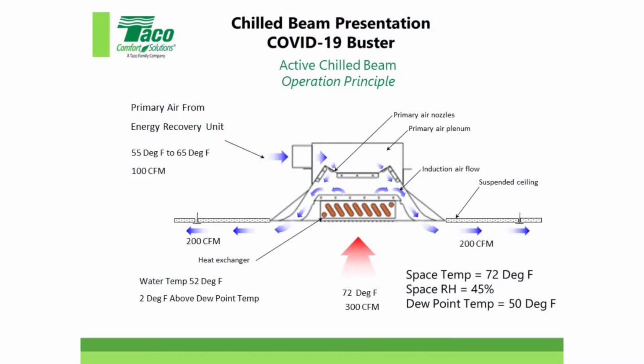I had to borrow this, so here's kind of the engineering associated with this. You can see right here the primary air coming from the energy recovery unit. There are different temperatures that you might be going in there. It's very gentle, very small. You're going to see an air flow pattern very shortly. And there's the induction. The air comes in right here, see how it comes in? It goes through some nozzles right here, induces the air to come up here, and then this gentle air comes down and just falls down into the zone.